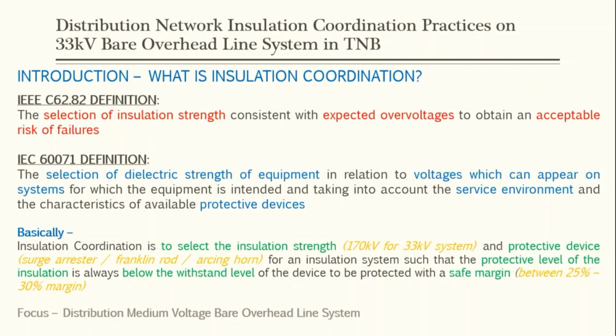For example, for 33 kV, the insulation strength can be up to 170 kV, right? And protective devices can include surge arresters, Franklin rod, arcing horns, right? And for an insulation system, the protective level of the insulation is always below the withstand level of the device to be protected with a safe margin. And in TNB, the safe margin can be between 25 to 30%. The focus for this knowledge sharing today will be on the distribution medium voltage bare overhead line system, because we also have substation insulation coordination. But I won't be talking about substations, because my area of expertise is on the distribution medium voltage overhead lines.